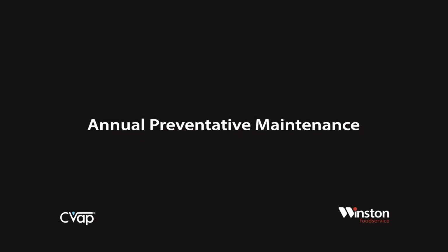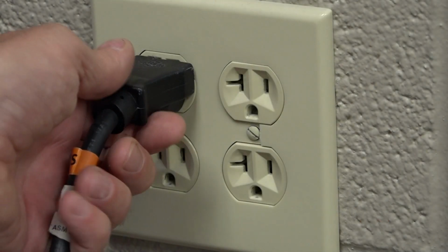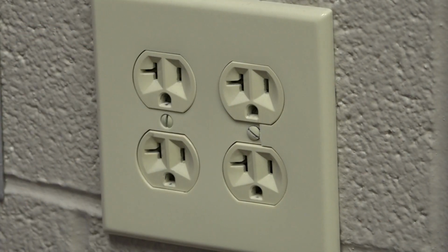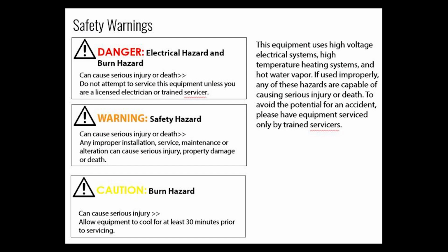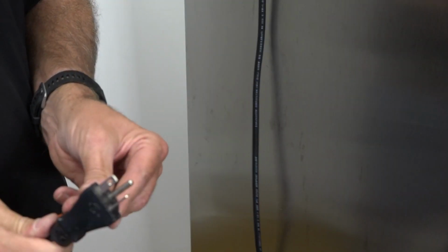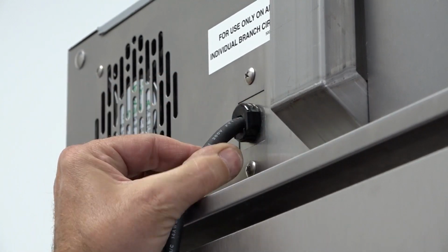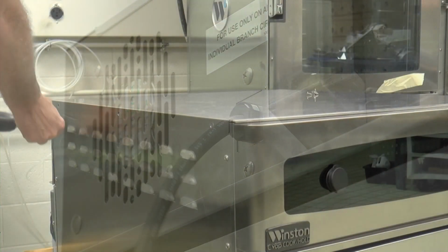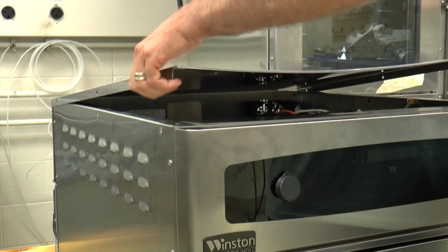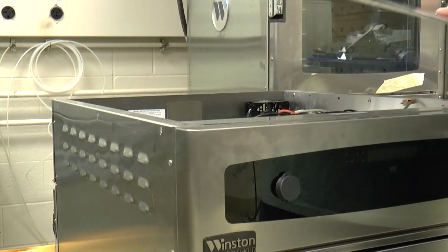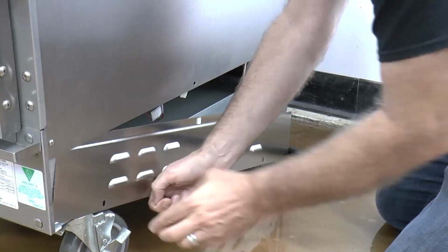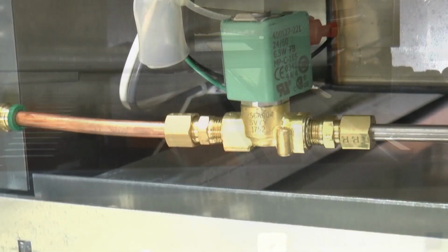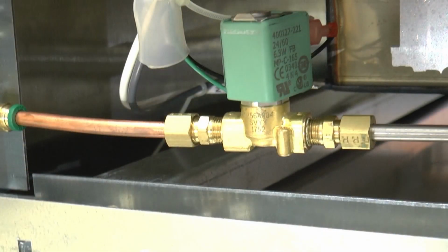Annual maintenance. With the unit disconnected from its power source, have an authorized service technician perform the following annual preventative maintenance. Inspect the power cord and plug for loose or frayed connections. Remove the top panel and inspect the wiring for loose connections or burnt wires. Remove the lower access panels and inspect internal plumbing, probe wires, sensor wires, and heater connections.